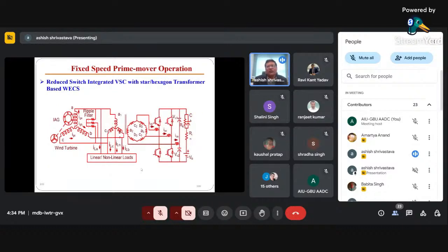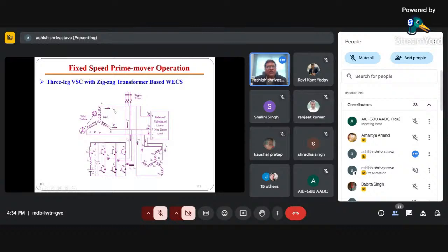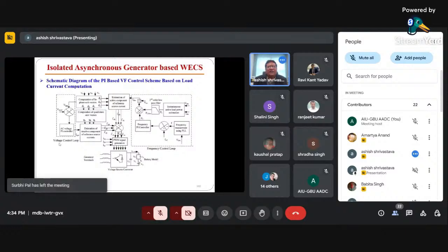This is another topology where the hexagon transformer is star on the primary side, that means on the turbine side, and on the converter side, that is the battery side, you have the hexagon. Six windings are there which are displaced by certain angles, 60 degrees each, 360 divided by 6. So this is a hexagon transformer. This is again a zigzag transformer to be connected with the VSC. This is the control algorithm.